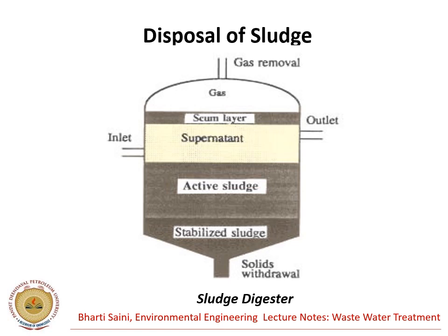Now let us discuss the different stages during the sludge digestion process. Basically, three different stages have been found during the decomposition of the unstable sludge into the stable form. First is acid fermentation, second is acid regression, and third is alkaline fermentation.